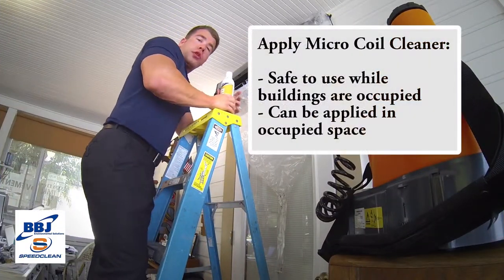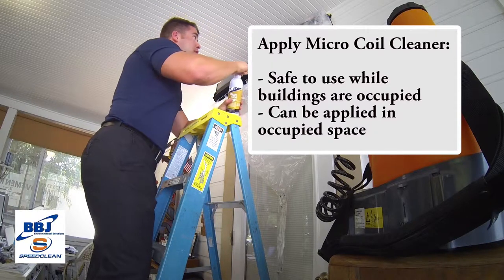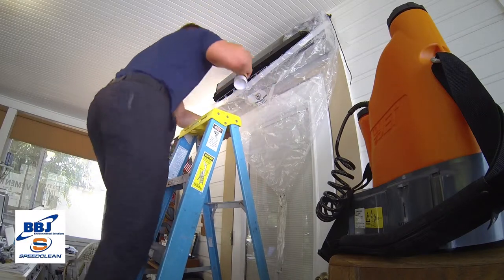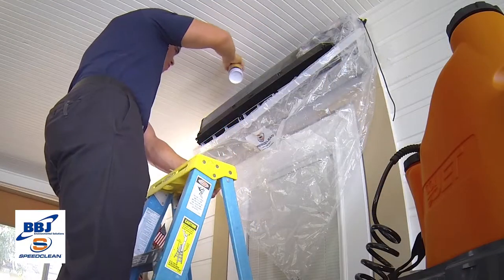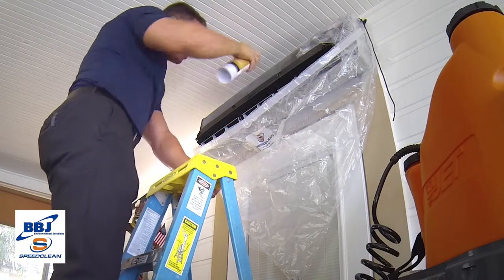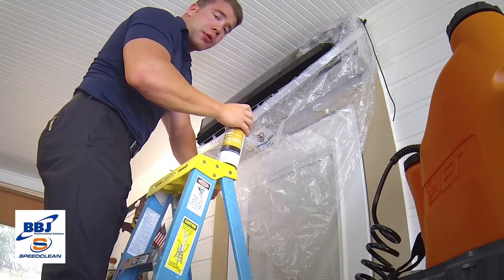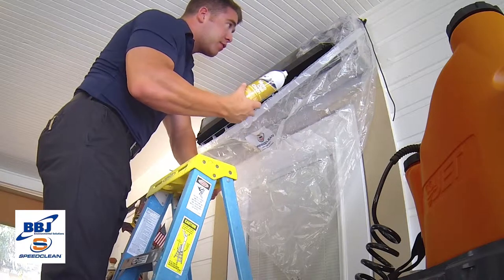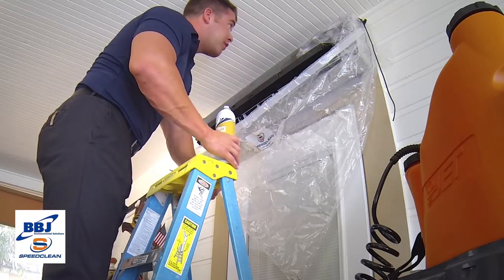Now that we've rinsed our coil and blower wheel, we're going to apply our micro coil cleaner by BBJ. You want to apply this rather liberally to all your coil surfaces and your blower wheel. Just like any other BBJ product, it's very people friendly and environmentally friendly, so you don't have to wear any extra protection that you might with other heavier chemicals.